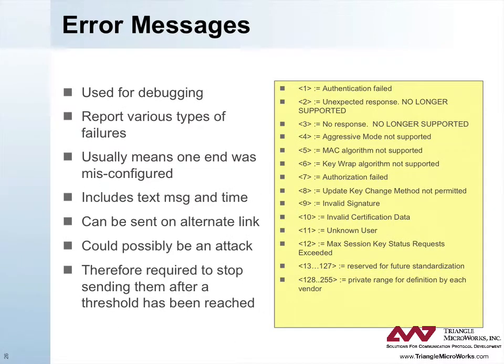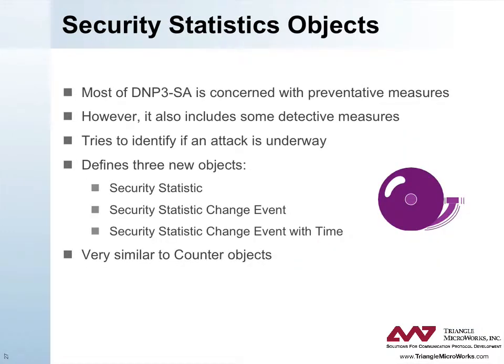Error messages report various types of failures and are often used for debugging. They include a text message and a timestamp and can be sent on an alternate link. An error message usually means that one end was misconfigured, although they could indicate some type of attack. Consequently, the specification requires that they stop being sent after a threshold has been reached. Most of DNP3 secure authentication is concerned with preventative measures; however, it also includes some detective measures in order to attempt to identify if an attack is underway. The specification defines three new objects for security.